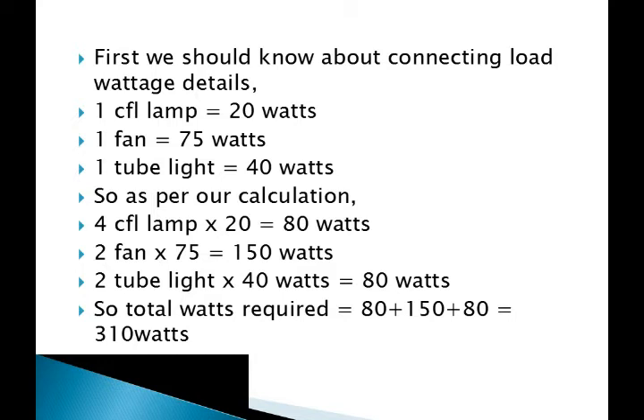First we should know our connected load wattage details. Usually one CFL lamp is 20 watts, one fan is 75 watts, and one tube light is 40 watts. As per our calculation, 4 CFL lamps at 20 watts each equals 80 watts, 2 fans equal 150 watts, and 2 tube lights equal 80 watts.